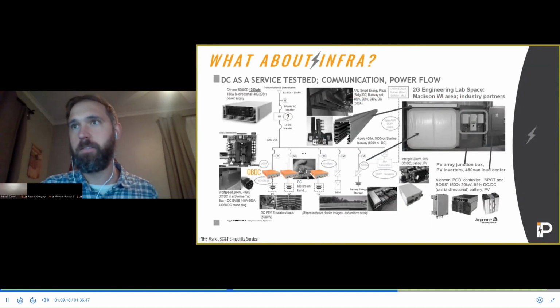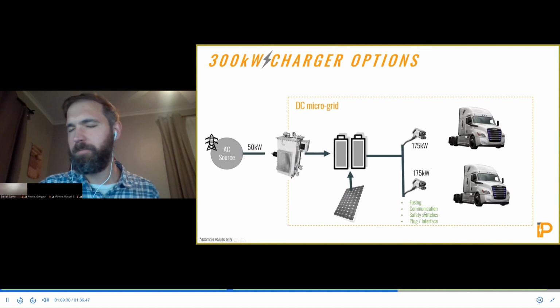You have to be very careful with your installation coordination, especially with existing infrastructure. I would imagine you'd still need the site-wide earth leakage to still be under the 20 milliamps or whatever the ground fault detection or interrupt needs to be, and that would become difficult with more trucks in parallel. But also, if you have multiple sources providing short circuit current, you have to be careful. If you have old infrastructure designed for 400 volts, it's designed for a different working voltage, so there are some caveats you have to be careful of. Yeah, this is great stuff for future gaps in codes and standards, showing what unintended consequences could happen if you reuse existing infrastructure in a manner not intended. And again, unfortunately, you're both right, Stefan, both statements have good points. Anyway, go on.